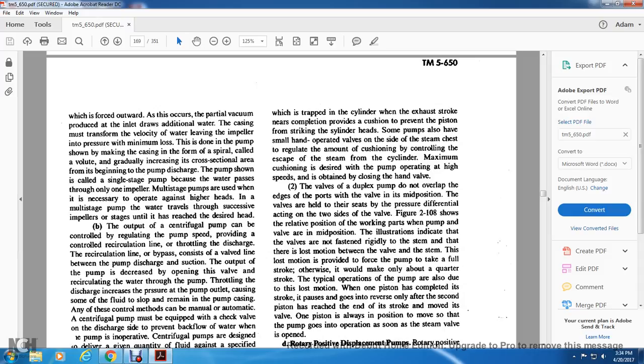Some of the pumps also have small hand operated valves on the side of the steam chest to regulate the amount of cushioning by controlling the escape of steam from the cylinder. Maximum cushioning is desired for a pump operating at high speed, obtained by closing the hand valve. The valves of the duplex pump do not overlap the edge of the port when the valve is in mid-position. The valves are held on the seat by the pressure differential acting on the two sides of the valve. Figure 2-108 shows the relative working position when the valve is in mid-position.